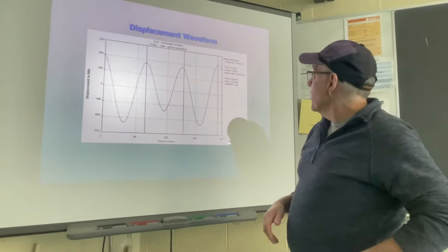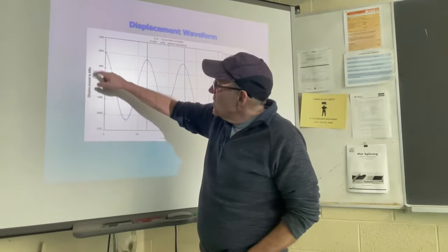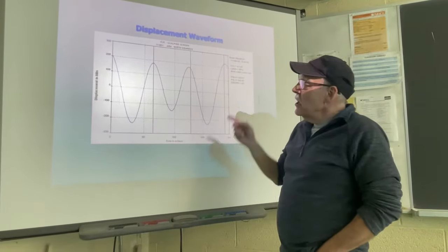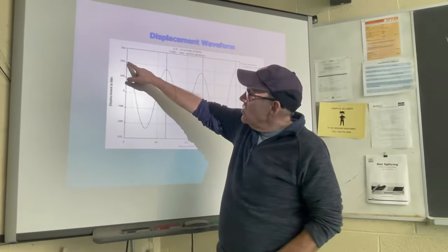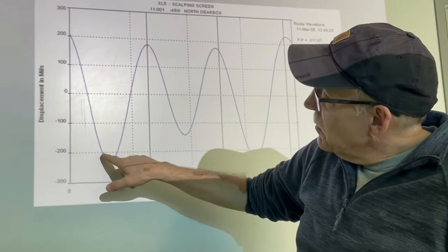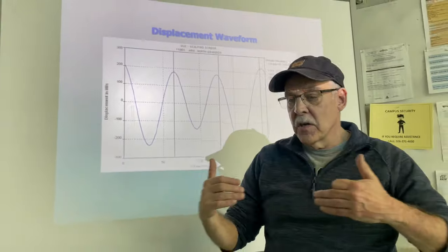So we know what the operating speed is. Now, this is our waveform. This waveform is in displacement in mils. A mil is a thousandth of an inch. So this is how we actually see how much this piece of equipment is vibrating. We can see 200 mil, that's 200 thousandths of an inch. Minus 200, that's 200.